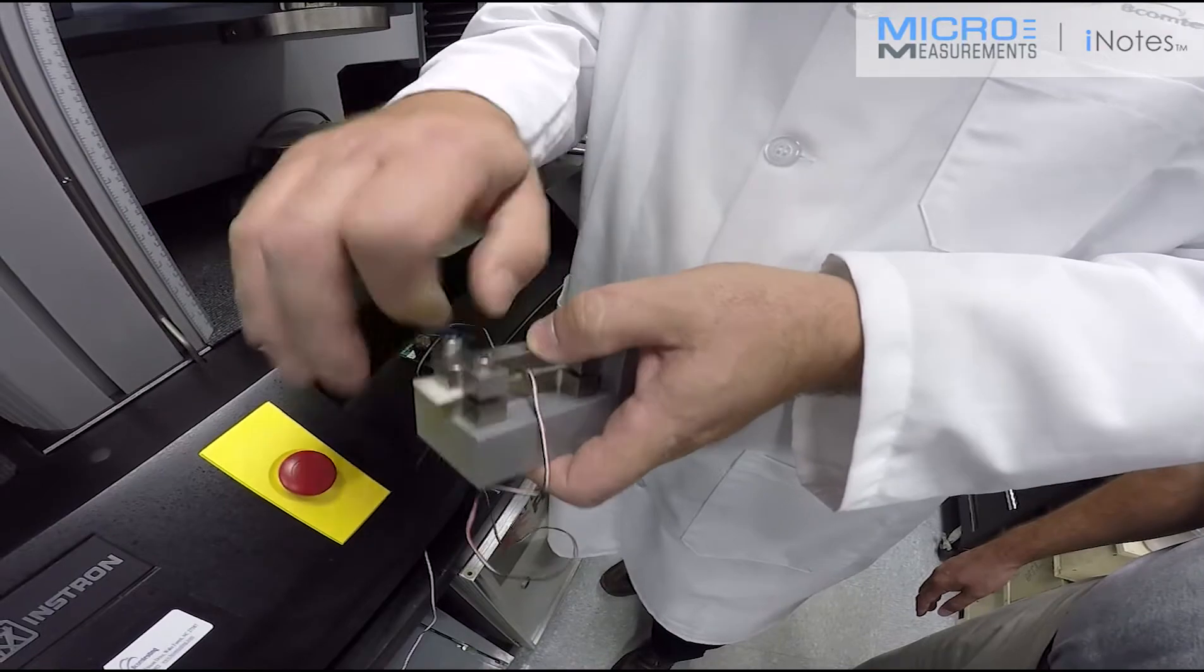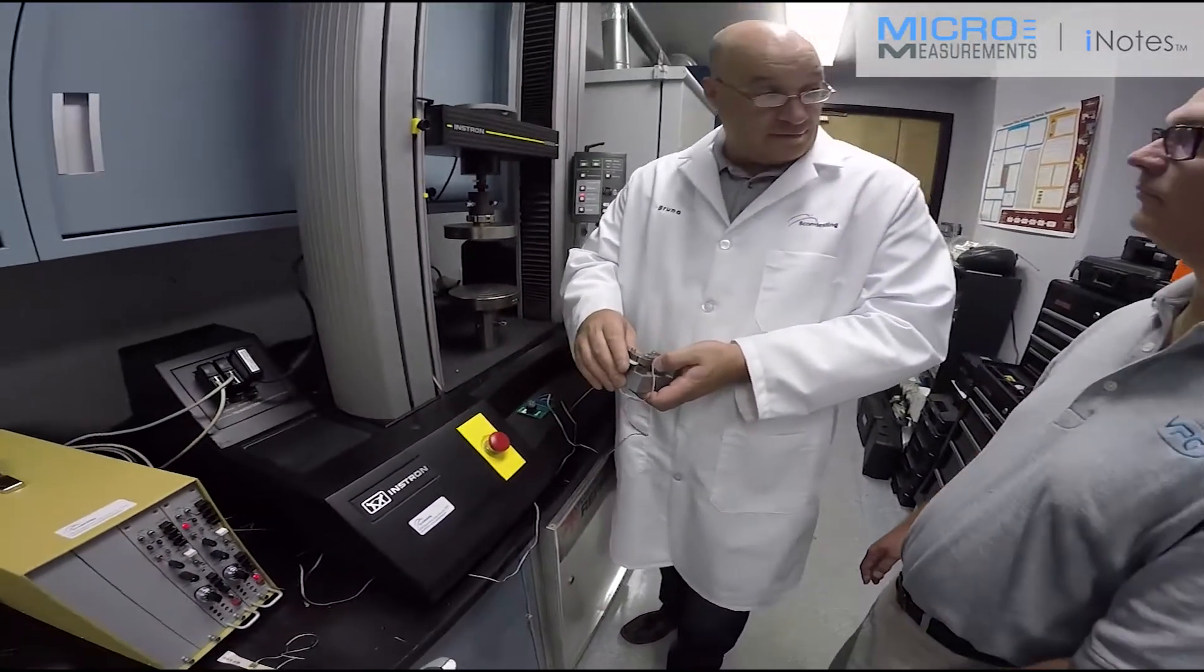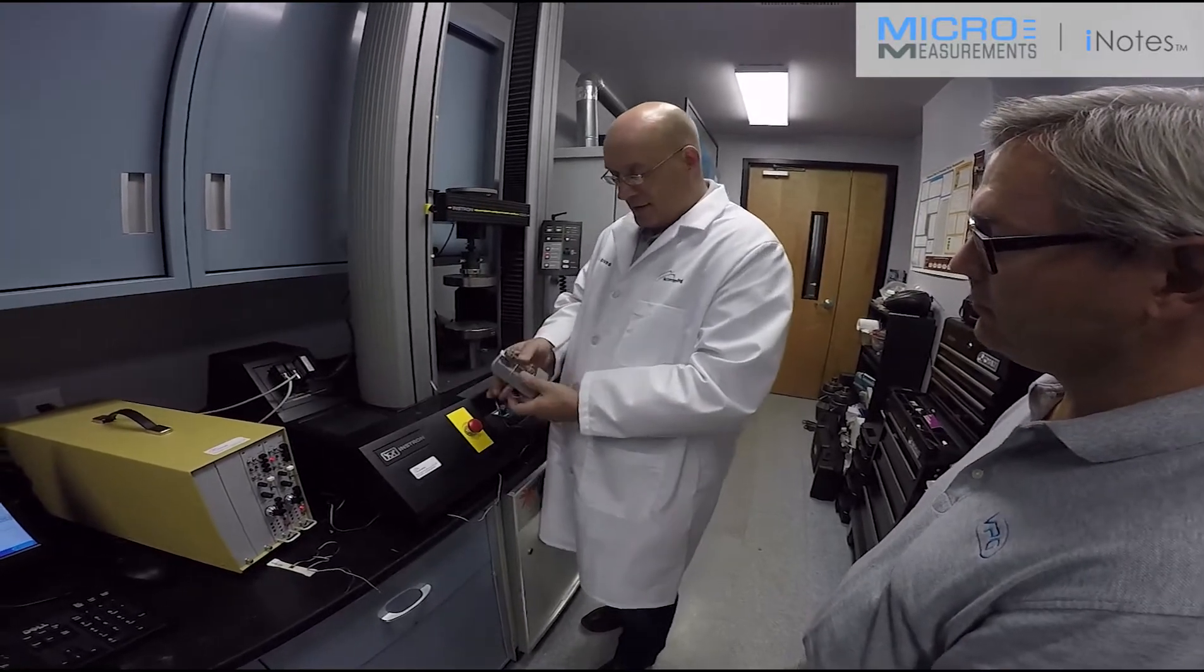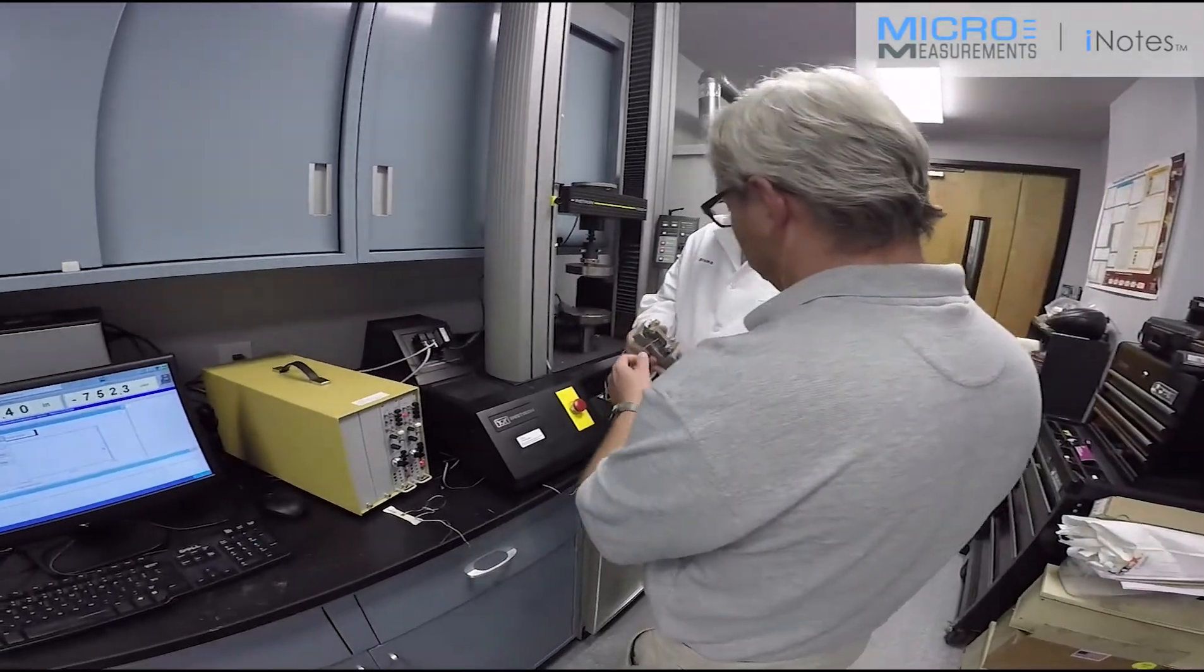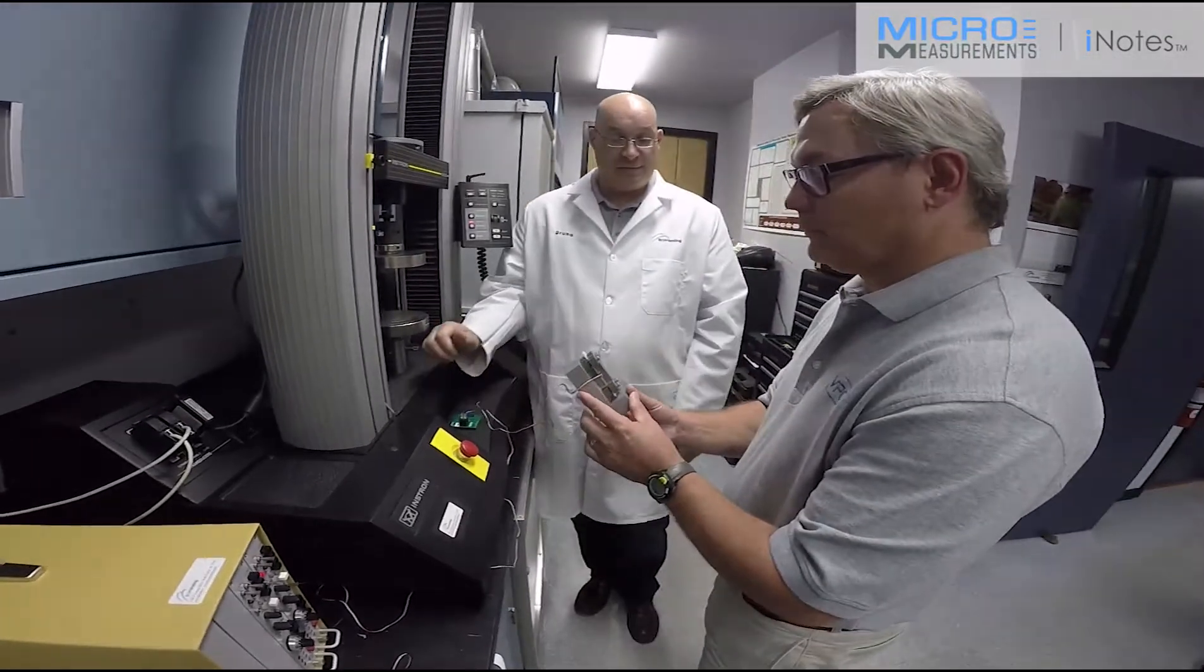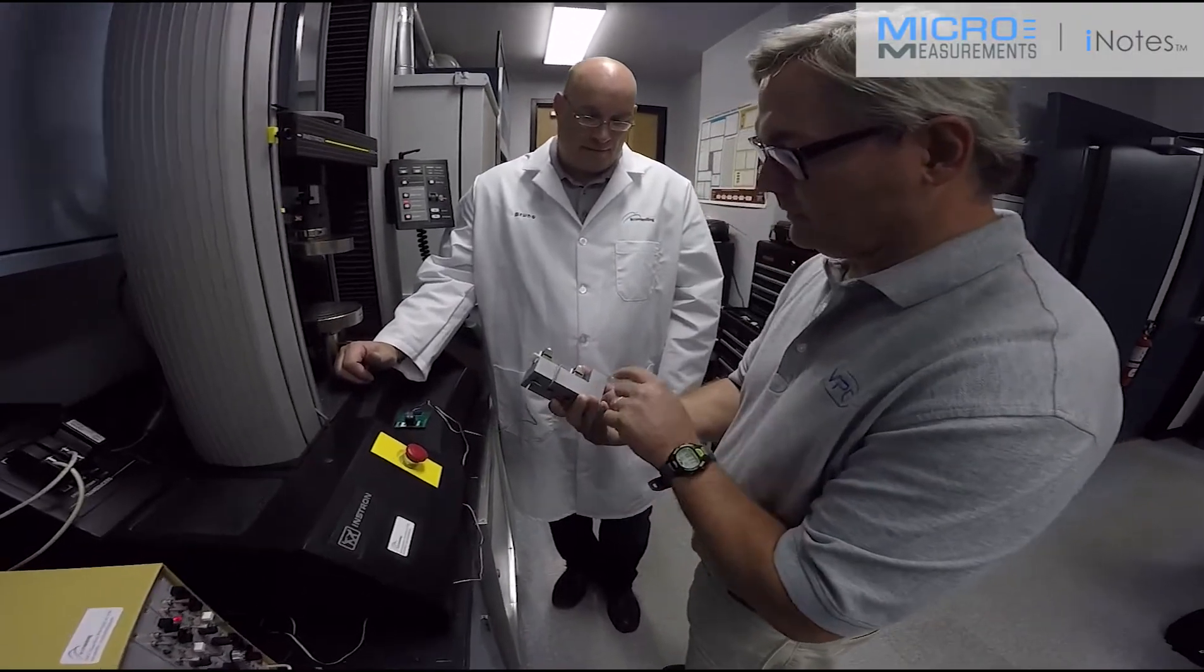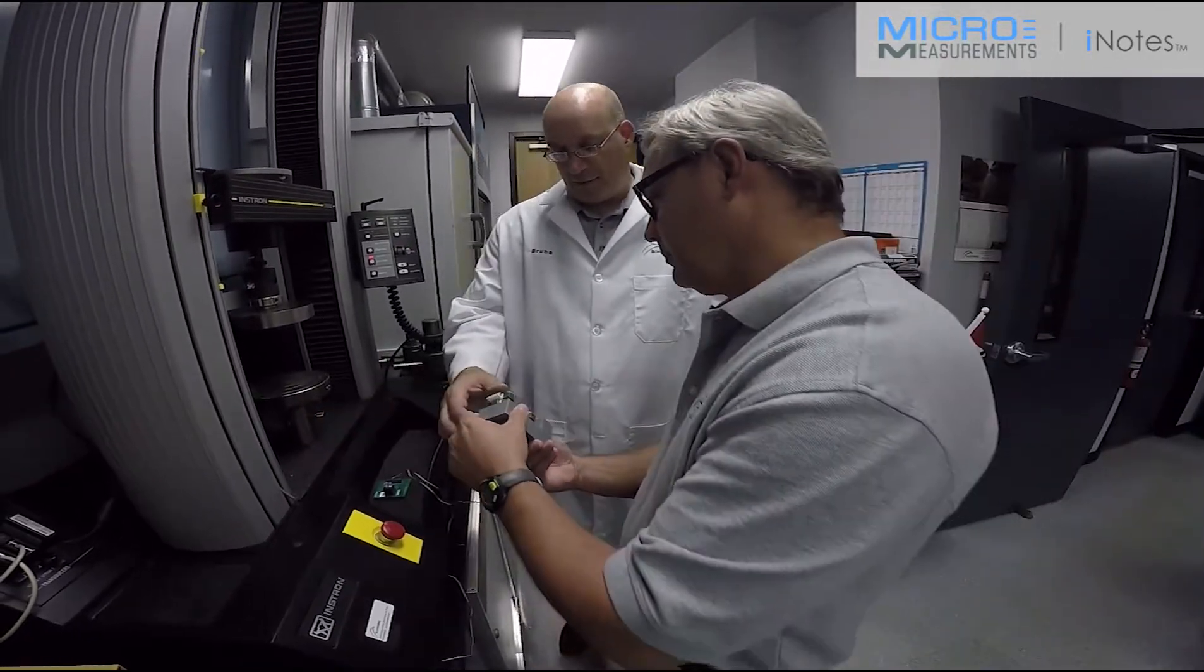In this case, I'm just going to hand-tie it. We're using a 2,000-pound frame for this test, which is not enough to take it to failure. We're not really interested in failure today. We're looking at modulus only. What we're going to do is hand-tie. We don't want to over-tie this, because at that point, you might be more testing your ability to compress the specimen in the fixture versus actually running the specific test. So it gets loaded. This bottom portion of this L-shaped piece of metal loads the bottom, and the top gets loaded by the platen.